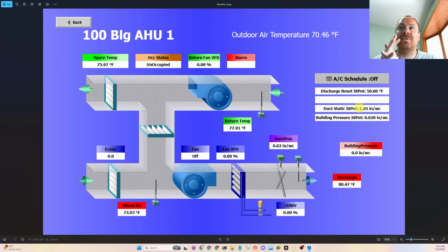We can see that some of these energy savings strategies, we could do a Guideline 36 duct static pressure reset on the supply fan. And when we would cut over the project and these big monsters would be left in place, the test and balance contractor would also validate that these fans push design airflows through the building. And then you would also redesign ventilation rates to bring the building up to code, basically. I'd have to check too.